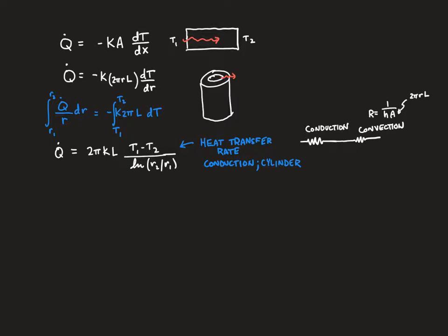As you increase the amount of insulation, you are reducing the conductivity, but you would be increasing the convection on the outside. For most practical purposes, if you want to insulate a pipe, for instance, it's still better just to add more insulation. But depending on the materials and actually for insulation itself, for the first little bit, as you add more insulation, it would be a better thermal conductor. More heat would transfer out because the convection component is winning.